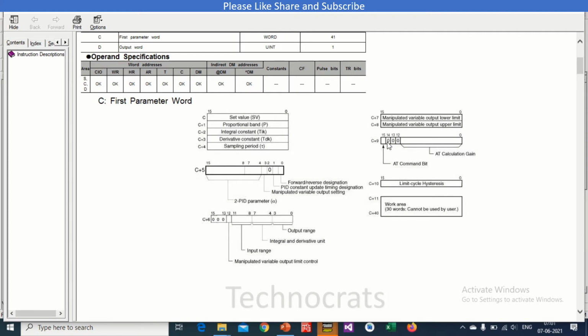Now auto tuning, C+9 bit 15 is for auto tuning enable, and it is auto calculation gain from 0 to 11. Now the limit cycle hysteresis, that is used for PID auto tuning, is also mentioned here. And C11 to C40 is restricted for use of user, so it's basically for the PID loop only.